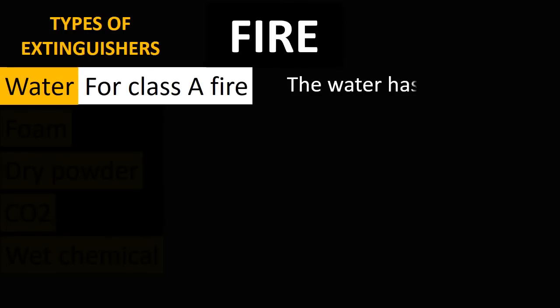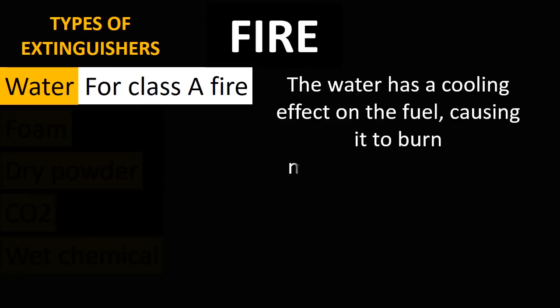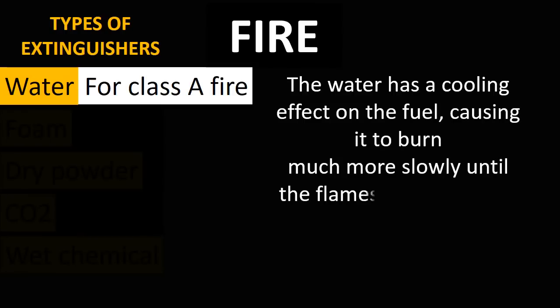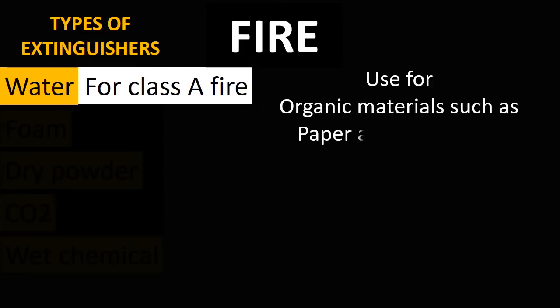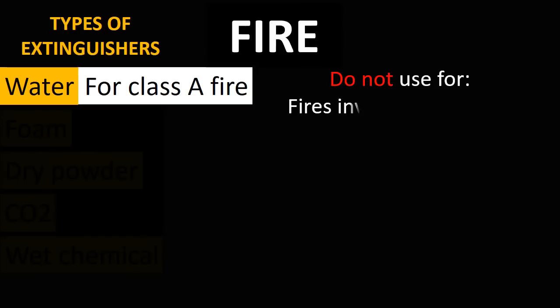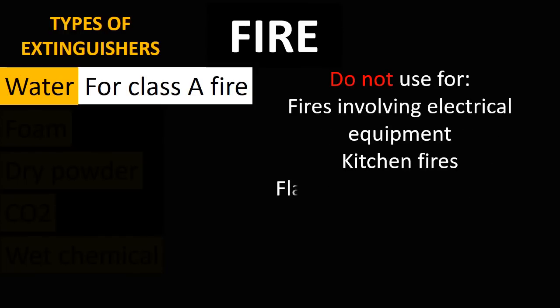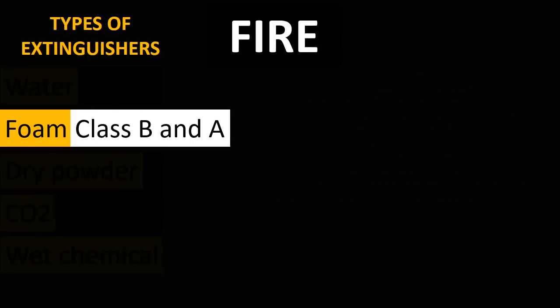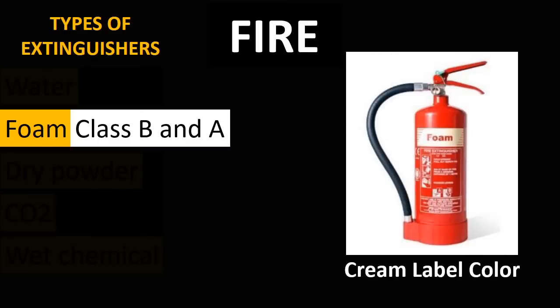Water has a cooling effect on the fuel, causing it to burn much more slowly until the flames are eventually extinguished. Water type fire extinguishers are used for organic materials such as paper and cardboard, fabrics and textiles, wood and coal. Do not use water type fire extinguishers for fires involving electrical equipment, kitchen fires, or flammable gas and flammable liquids.